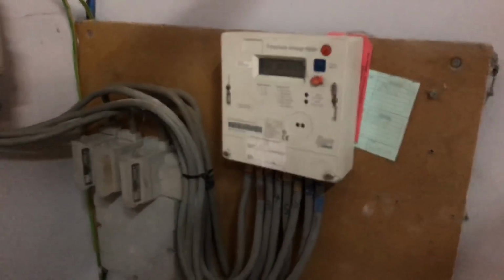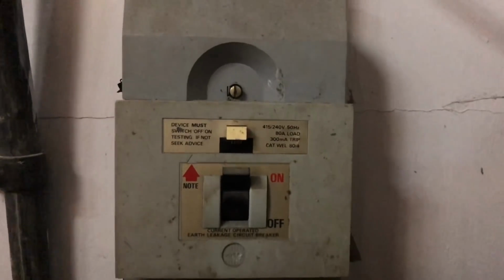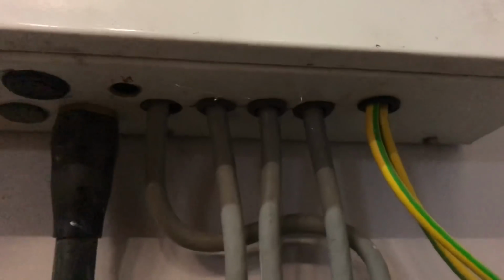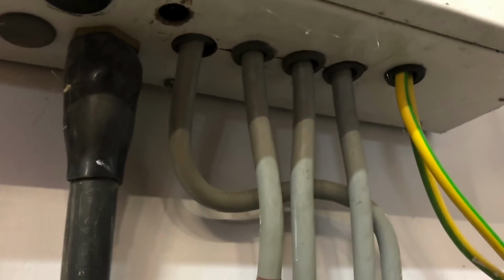So here's the incoming supply, and this is the dodgy RCD we're talking about, which doesn't trip when you press the test button. But up above, where the tails come in, this is what I'm talking about - eddy currents, not sure, because they've cut a tiny little slot in between each hole.